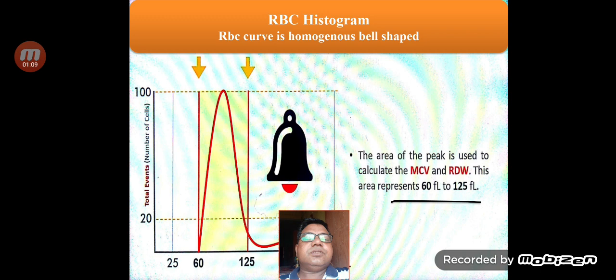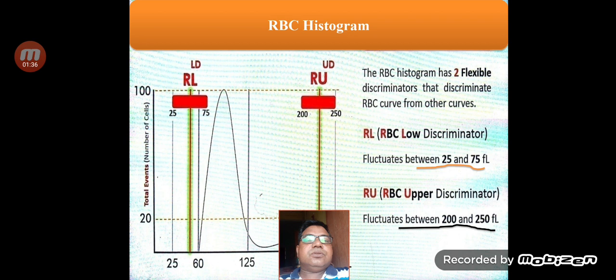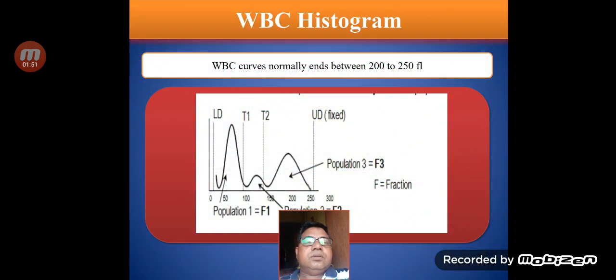In the RBC histogram there are basically two discriminators which discriminate this curve from others. The first discriminator is called the RL or lower discriminator, and the second is called the RU or upper discriminator. The RL fluctuates between 25 to 75 femtolitres, while the RU fluctuates between 200 and 250 femtolitres.